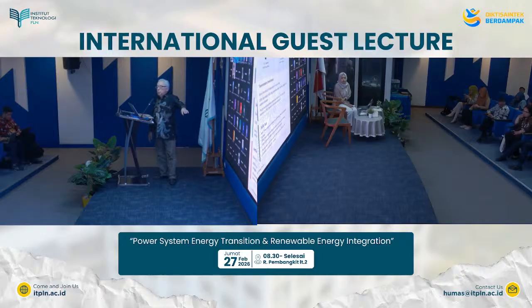Because the Java Bali system is coal energy dominant, the inertia is high, right? That's because it's got spinning inertia, represented by H, the inertia constant. Now, as you retire coal and replace it with solar or wind, the inertia will go down, because these new systems have zero inertia, so the average inertia reduces. So when you retire a coal plant, you have to replace it with something that will increase the inertia of the system, and there are ways of doing it.